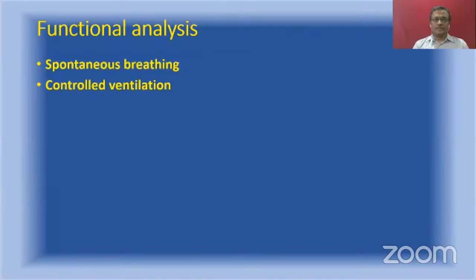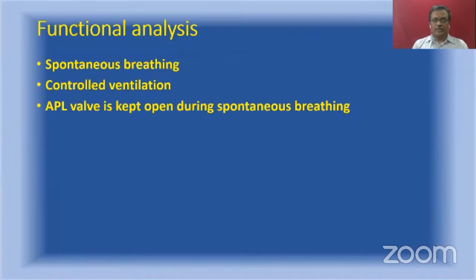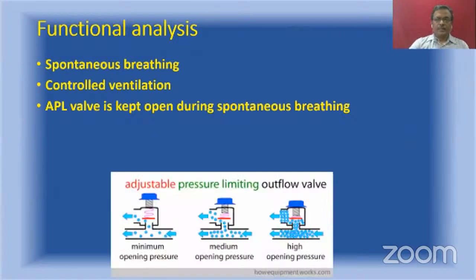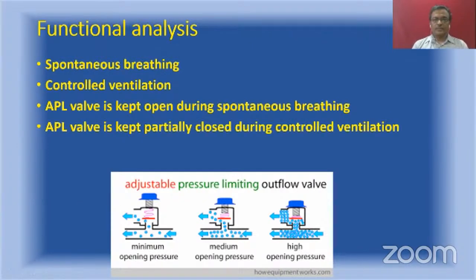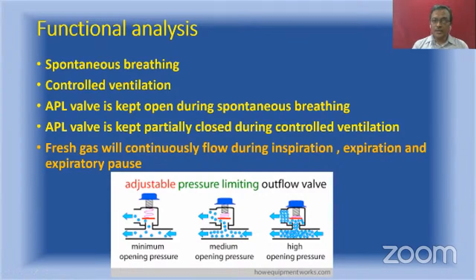Whenever you say function analysis, you have to say it under two headings: during spontaneous breathing and during controlled ventilation, right? A few points you have to keep in mind are, during spontaneous breathing, the APL valve is always kept open, like this. You can see in the picture on the left side, the valve is kept open. And during controlled ventilation, the valve is kept partially closed. Another important point is, fresh gas will flow continuously during inspiration, expiration, and expiratory pause. So there is no interruption of fresh gas flow, whether it is inspiration, expiration, or pause. The fresh gas will continuously flow into the circuit.